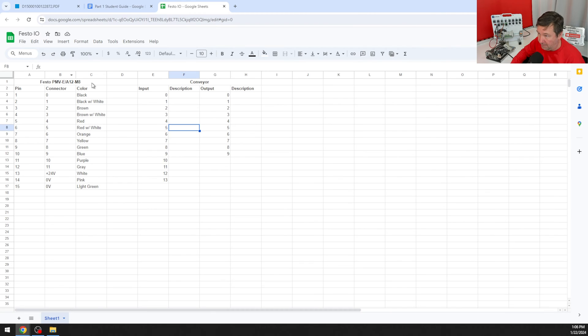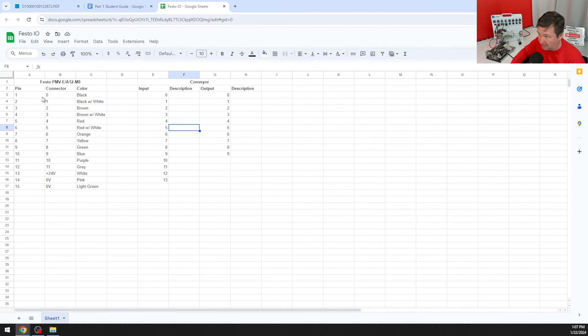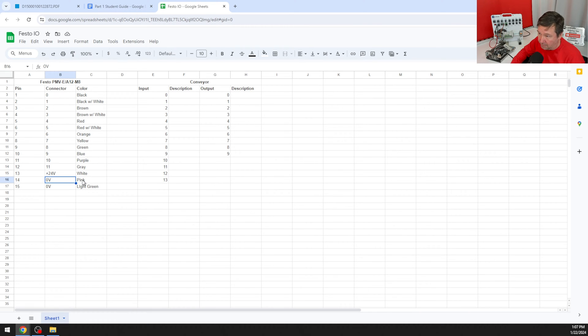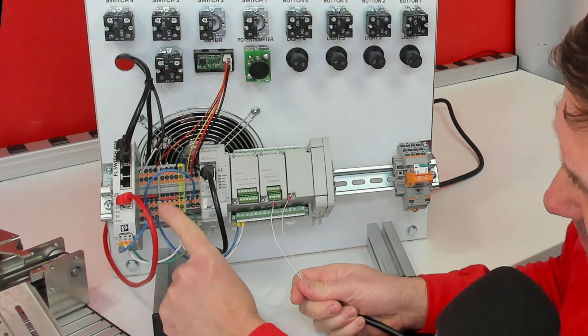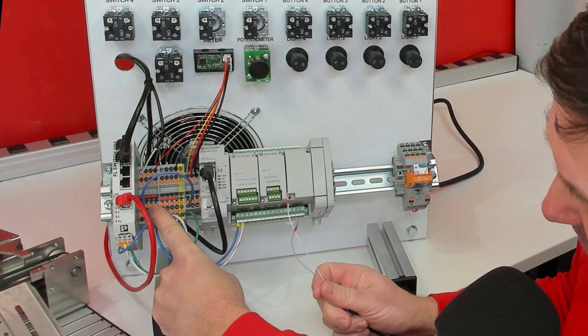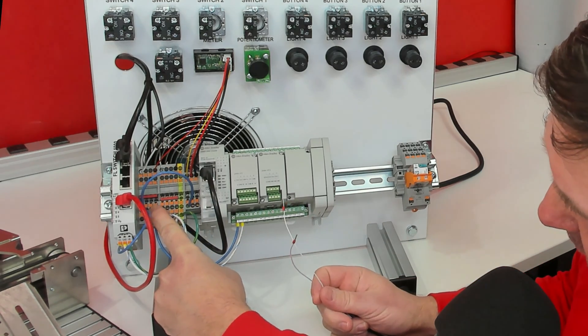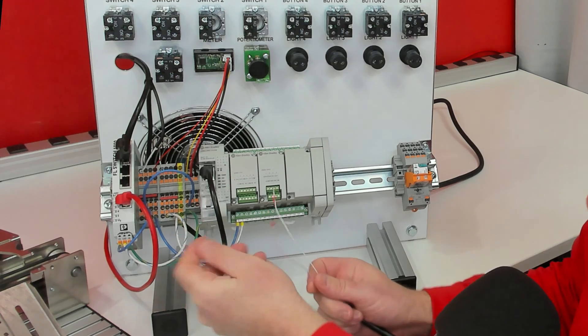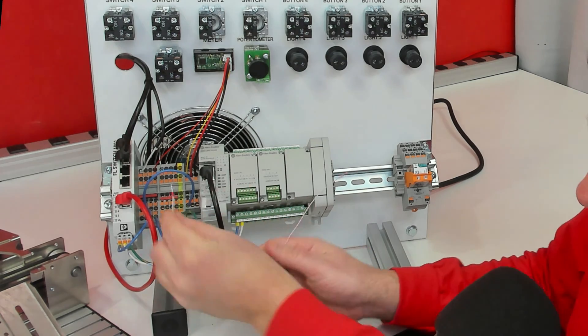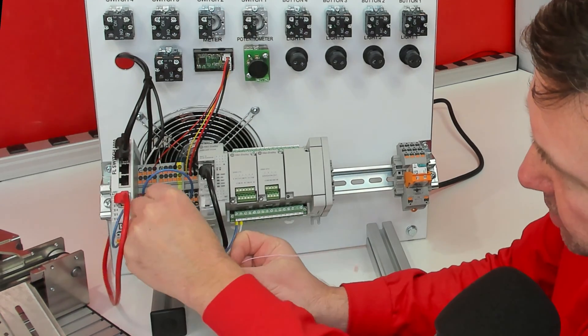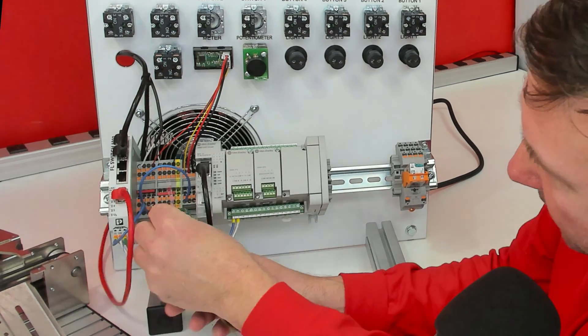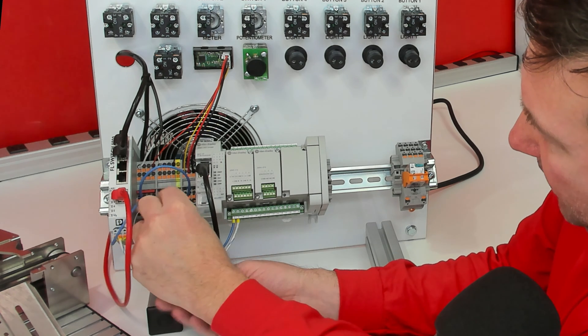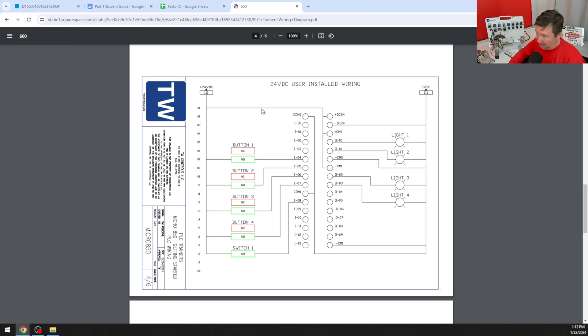I've already figured out the color codes of this particular cable and if you need this cable I'll put a link to one you can use down in the description but plus 24 needs to be on the white wire and 0 volt needs to be on the pink wire. On our PLC trainer the left set of terminals is the plus 24 volt the right set is the 0 volt so I'm going to take the white wire push it in and the pink will go into one of the minuses.